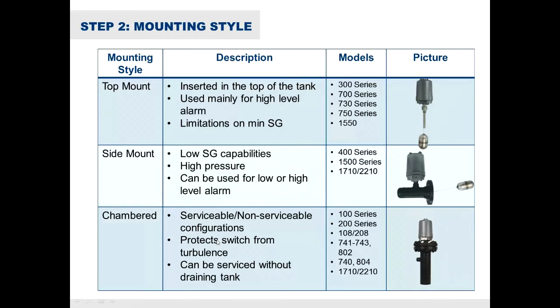The third mounting style is chambered. Chambered can be serviceable or non-serviceable. If serviceable, there's a flange connection between the electronics and inside the chamber, allowing you to access and swap out the float to service or clean it. Non-serviceable would be a sealed chamber — typically less expensive, but you lose the capability of servicing the inside. A chambered level switch also protects from turbulence; installing it into a separate chamber mitigates turbulence, protecting the float and preventing false trips for a more stable level reading.